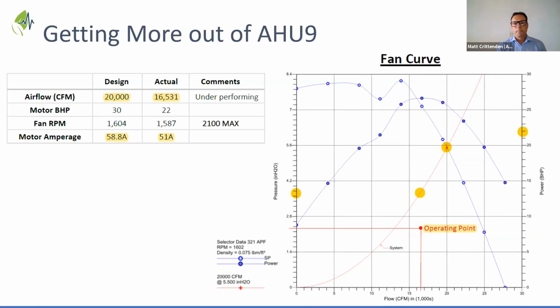Okay. But that being said, things should line up a lot better, even given what we've provided. What we do know, what we can say is constant, is the RPM and the CFM. So that's the nuts and bolts right there. Also, what's not up there, what you should also look at is the cooling coil velocity. Even though that fan says it can do 20,000 CFM, at 20,000 that coil velocity is going to be over 500-something feet per minute. So maybe you've got your airflow, but now you've got humidity level problems, and you don't want that at all in a hospital.